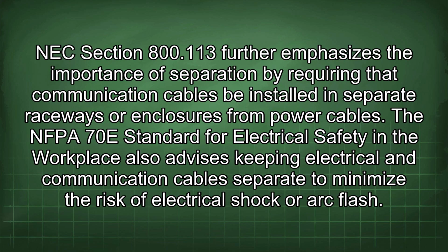NEC Section 800.113 further emphasizes the importance of separation by requiring that communication cables be installed in separate raceways or enclosures from power cables. The NFPA 70E standard for electrical safety in the workplace also advises keeping electrical and communication cables separate to minimize the risk of electrical shock or arc flash.